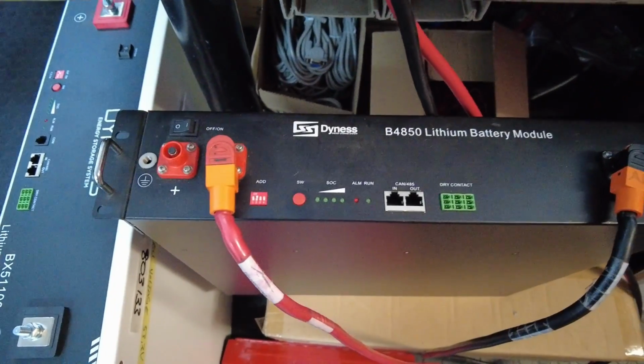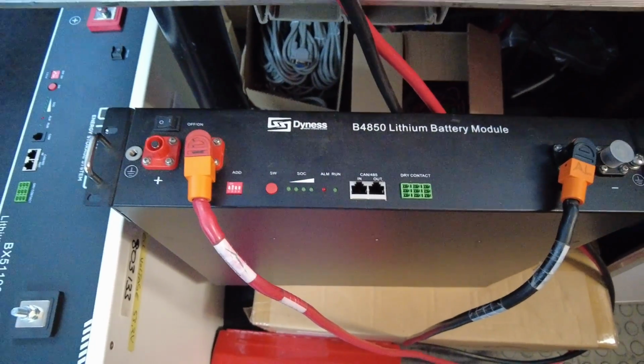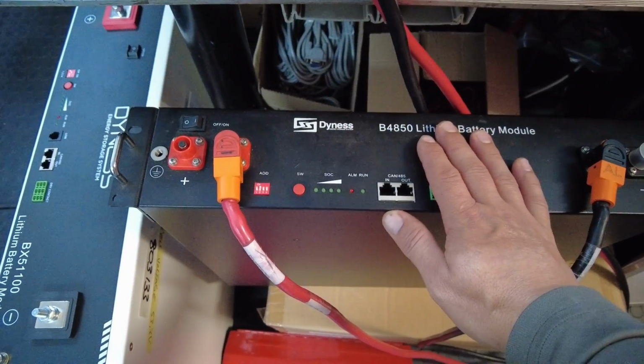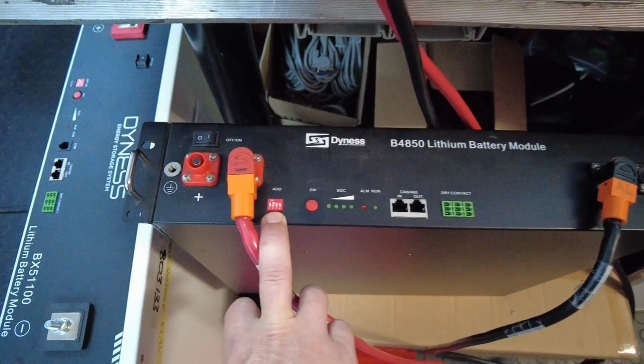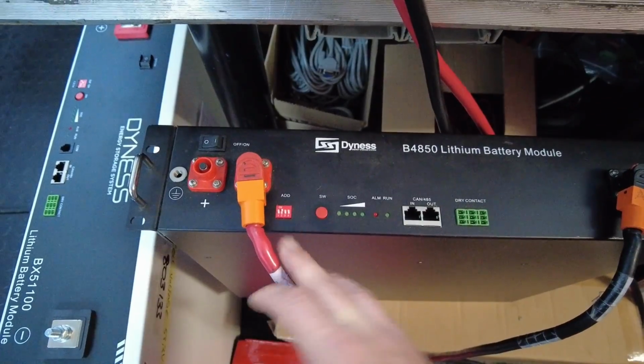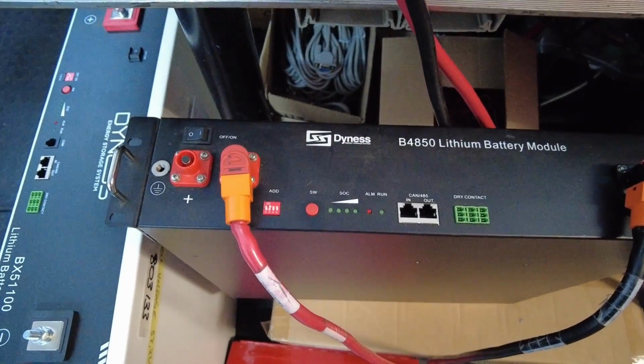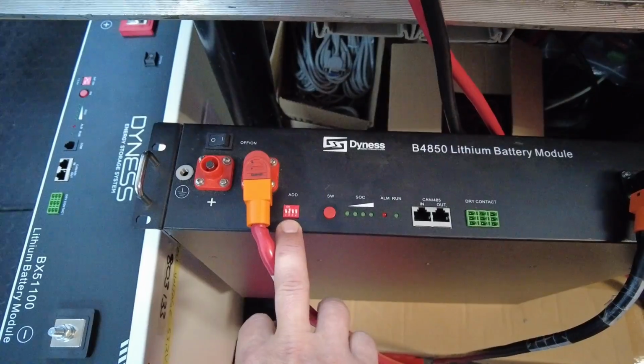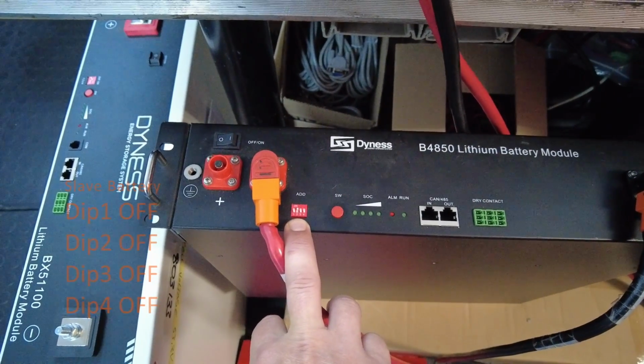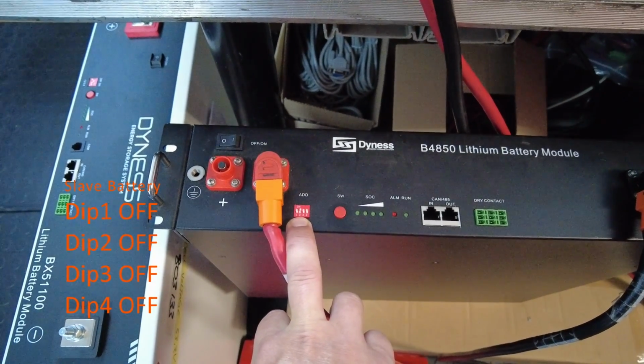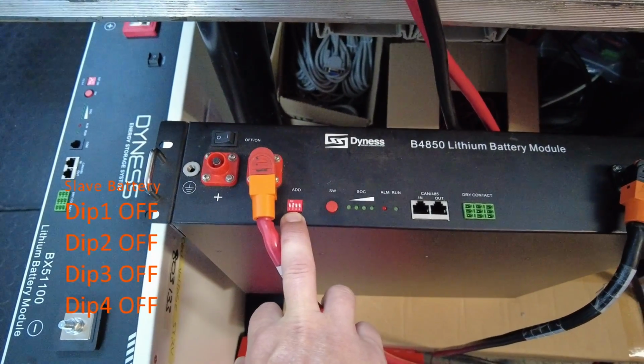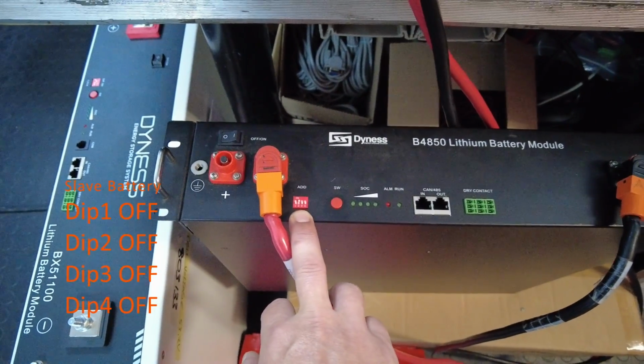As for your slave batteries, when you connect multiple batteries in parallel with this one, it's only the master battery that has this dip setting. All of the following slave batteries should be set to all off. In other words, dip 1 off, dip 2 off, dip 3 off, as well as dip 4 off.